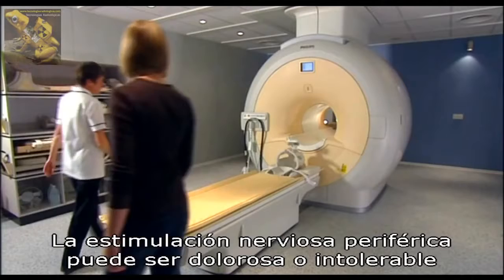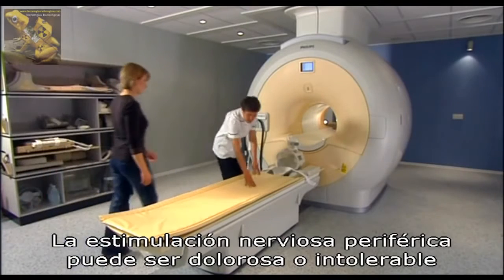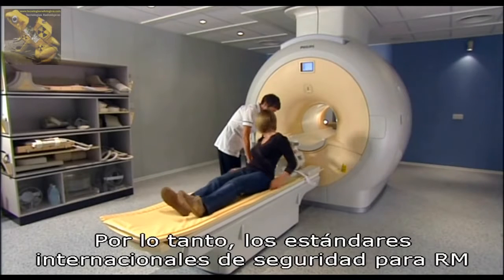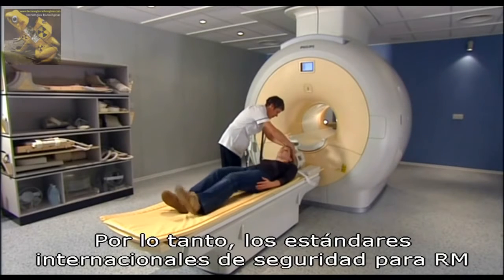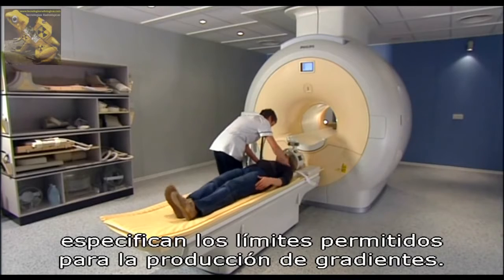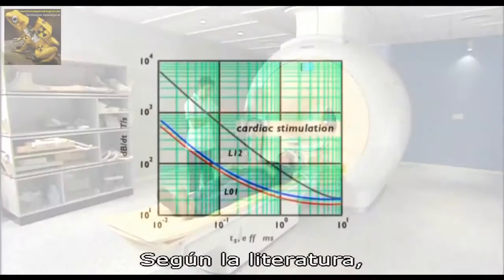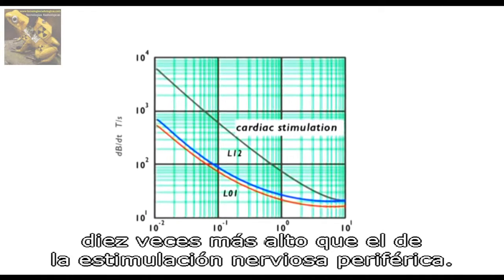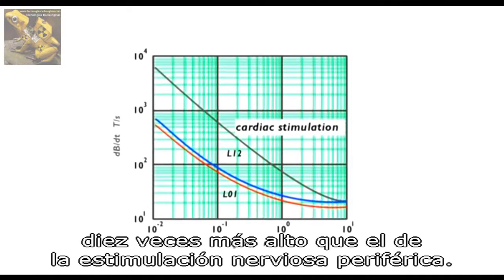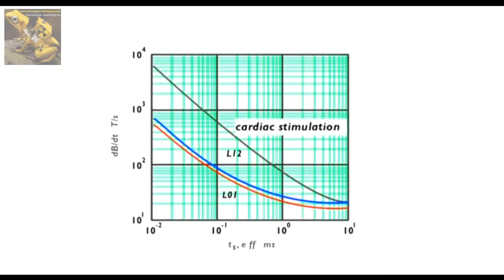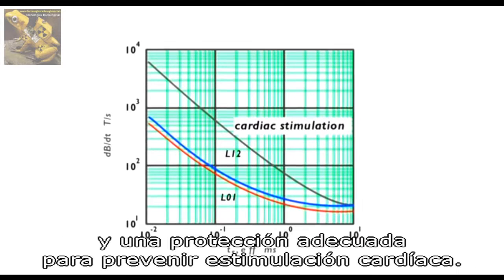Peripheral nerve stimulation can become painful or even intolerable at the stronger gradients of modern MR systems. Therefore, international MR safety standards specify limits for the allowed gradient output. From the literature it is known that the threshold level for cardiac nerve stimulation is about a factor of ten higher than that for peripheral nerve stimulation. Consequently, the occurrence of peripheral nerve stimulation provides a good warning and protection level for preventing cardiac stimulation.